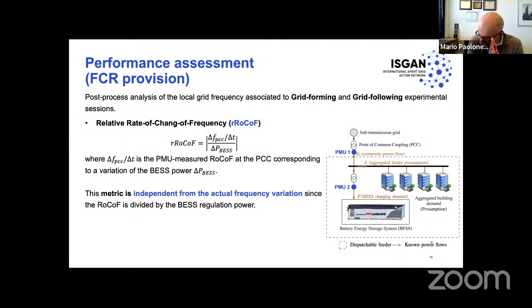Now, how have we quantified the impact of controlling the battery as a grid forming versus grid following unit? The metric we used is the relative ROCOF, or relative rate of change of frequency. It's simply the ratio between the ROCOF—the delta frequency at the PCC over time—divided by the amount of power the battery injects for primary frequency control, essentially expressed in hertz per second per watt.